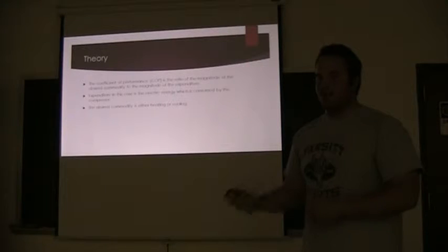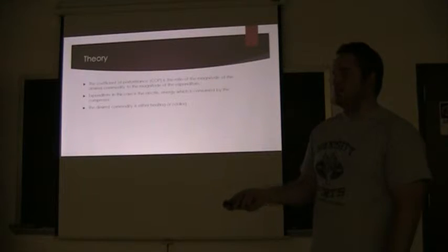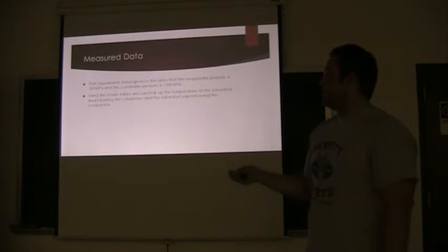The theory behind the whole coefficient of performance is basically what you're putting in and what you're getting out. In this case, what we're putting in is electric energy, and what we're getting out is heating or cooling. As lead, I was asked to determine what our COP was for 500 and 1200 kPa. The 500 would be coming out of the evaporator, and the 1200 would be coming out of the condenser. And we needed to use the steam tables to calculate the COP.